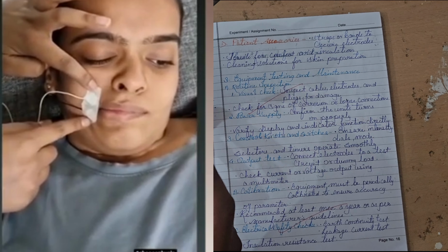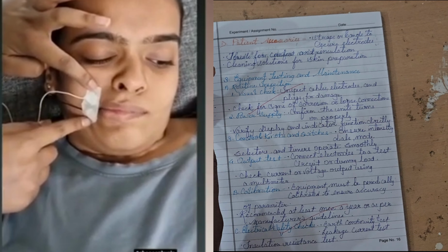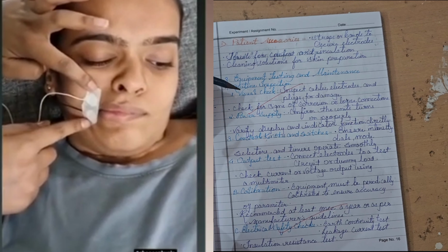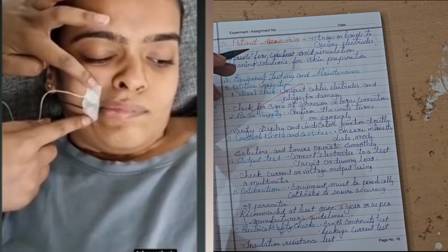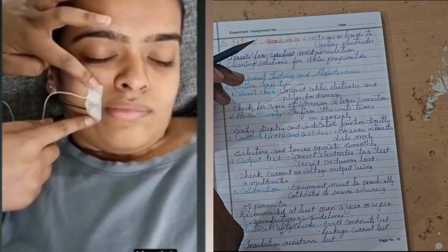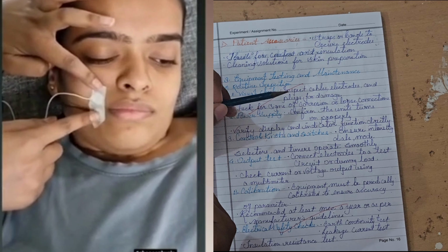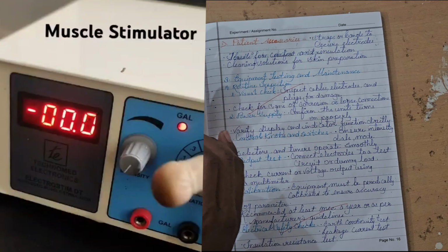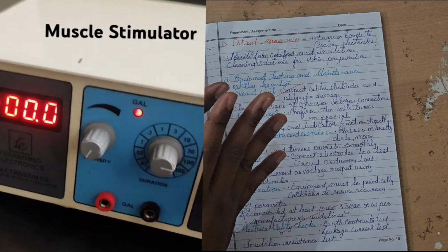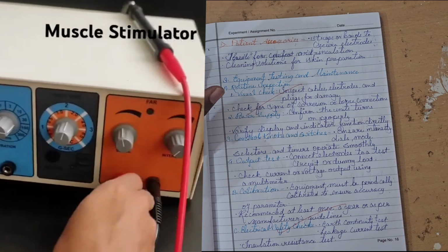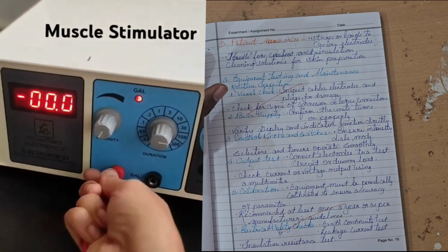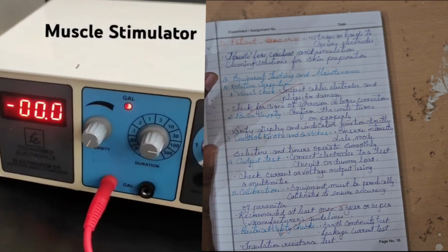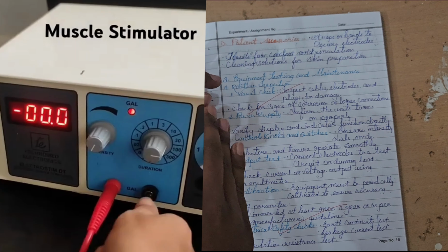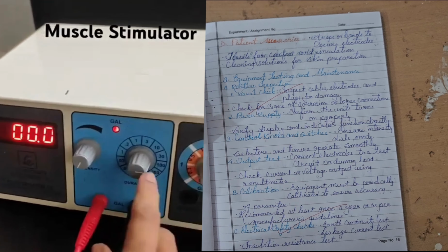The equipment testing and maintenance, routine inspection. Before applying to the skin, we can check whether the machine is working properly or not. So first, routine inspection. In routine inspection, what can you check? Visual check: you can see with your eyes, inspect the cable, electrodes, and plugs for damage. You can check that the cable, electrodes, wire, and all equipment are good or not. Power supply: confirm the unit turns on properly. The current will go through the cable to the machine and from the machine to the wire on the body; it should be good or not.